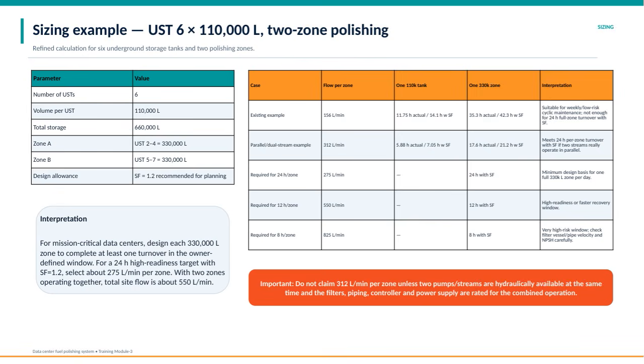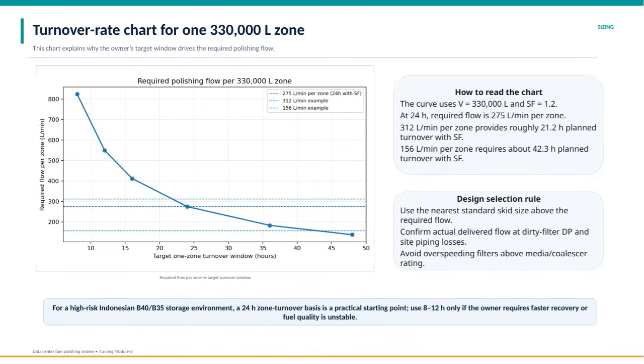Overall, careful sizing is essential to maintain fuel quality and ensure reliability in critical operations. This turnover rate chart illustrates the relationship between the required polishing flow and the owner's target turnover window for a 330,000-liter zone. Essentially, the target window set by the owner directly influences the flow rate needed to achieve that turnover. To read the chart, we're using a volume of 330,000 liters and a safety factor of 1.2. For example, if the turnover window is 24 hours, the required flow rate is 275 liters per minute per zone.